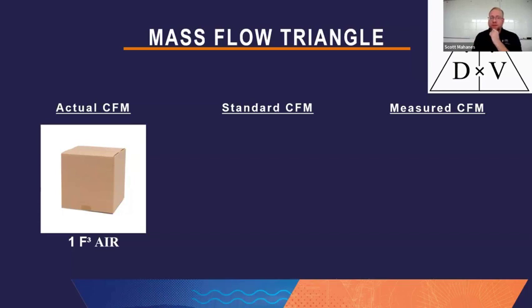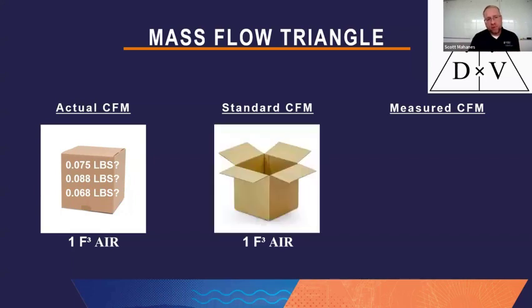That's what I'm ordering. But what I don't get guaranteed is the amount of mass of that air. It could be standard, it could be a little bit higher, it could be lower. I'm not asking for the mass. I'm only asking for the volume in the case of ACFM. When it comes to ordering 1 cubic foot of air under SCFM terms, though, the box is open because there's no surprise. It's the same size box, same volume, but also it's the same mass. So as you can see by this example alone, ACFM or volumetric flow rate by itself is not specific enough as a targeted value, whereas mass is, standard CFM is, because we know both the volume and the mass combined.